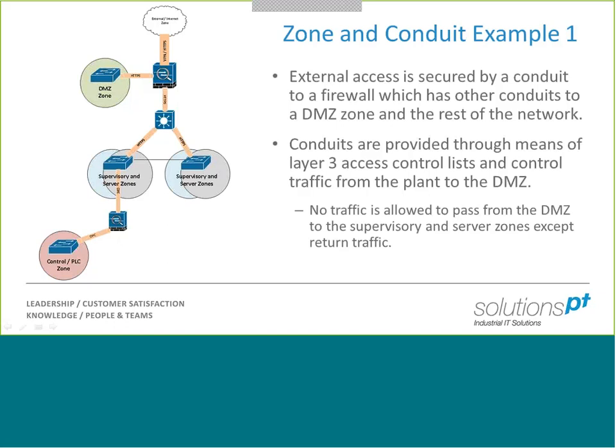We're making use of a secure protocol here, HTTPS, and imagine we're using one of the later SCADA packages that makes use of that and is able to offer a lot of functionality through a web browser. So we've got HTTPS allowed through there to our supervisory and server zones. Perhaps we've got web servers there, so from our server zones we may need to access a web server in a DMZ, but nothing else is allowed through, so there's no devices here with outbound internet access.